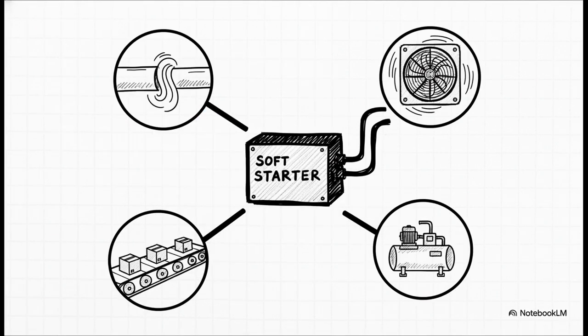So where does that simple, reliable soft starter really shine? It's perfect for things that need a smooth start, but then just run at one constant speed for a long time. Think about a big water pump, where a sudden start would cause water hammer jolts in the pipes, or a conveyor belt, where a jerky start would spill everything all over the floor. It starts gently, then just runs at full blast.